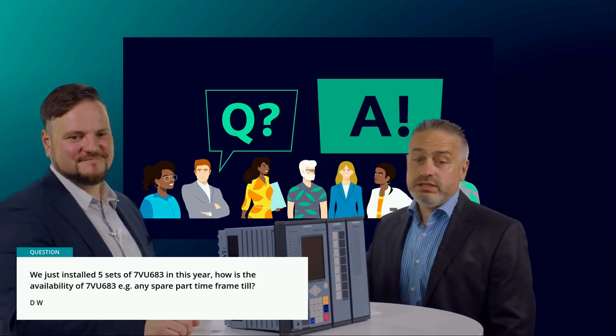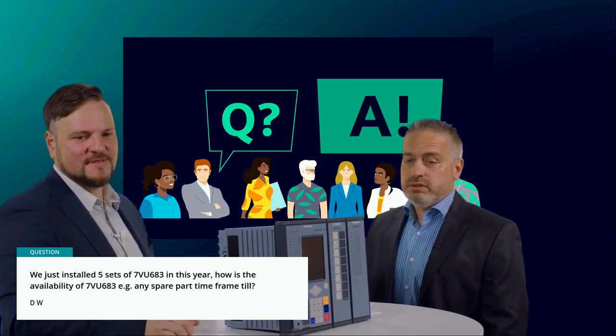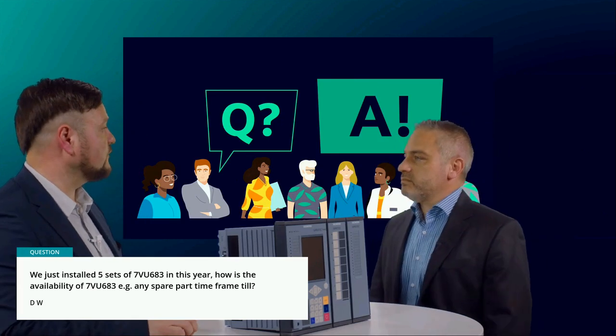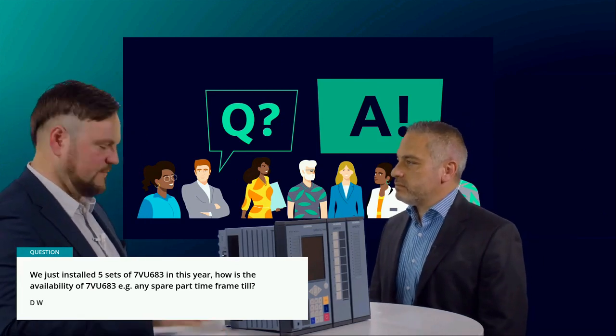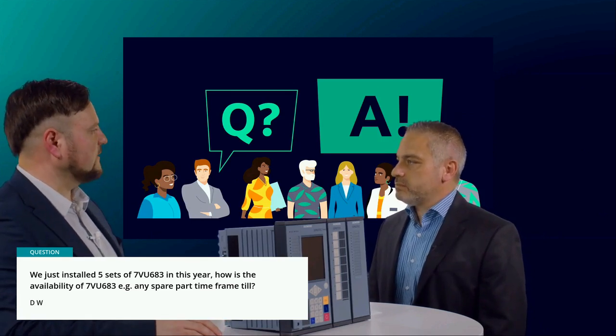We just installed 5 sets of 7VU683 this year. How is the availability of 7VU683? Any spare part time frame? Yes. This is our discontinuation process, our phase-out process. That means you can order the 7VU683 until September next year, normally. After that, we provide a repair service and a replace service in case of a fault, or in case the device is broken, we can offer a special spare part for this device. This is provided for up to 10 years.